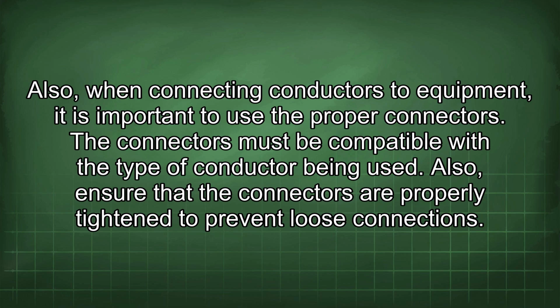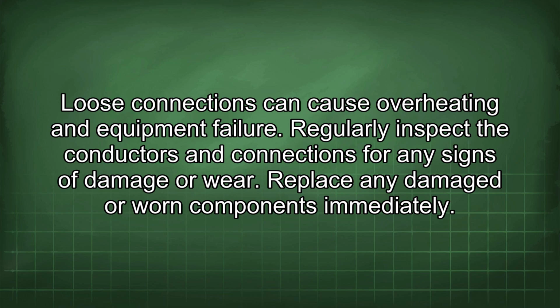Also, when connecting conductors to equipment, it is important to use the proper connectors. The connectors must be compatible with the type of conductor being used. Also, ensure that the connectors are properly tightened to prevent loose connections. Loose connections can cause overheating and equipment failure.